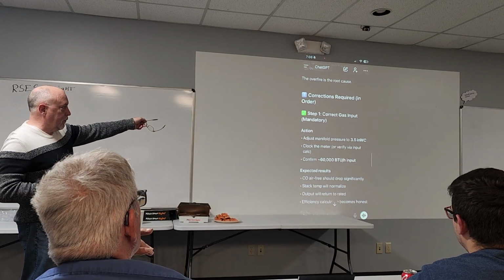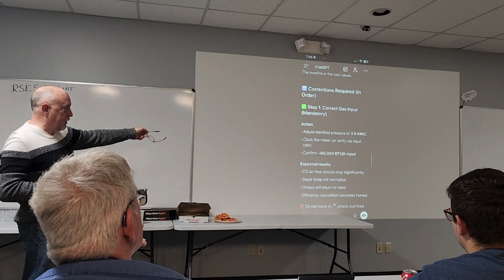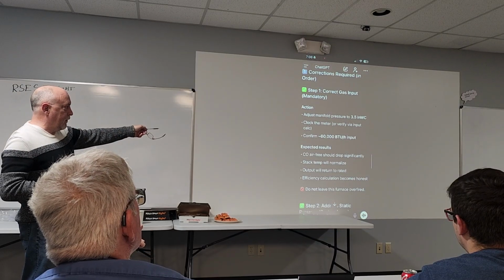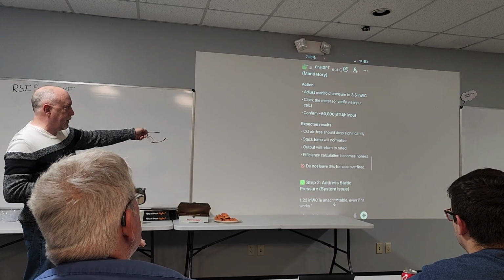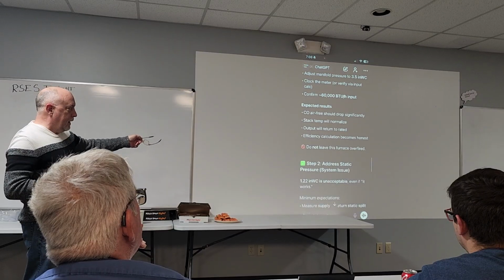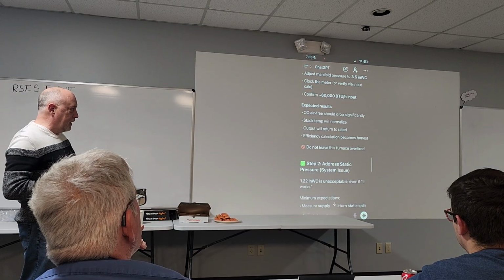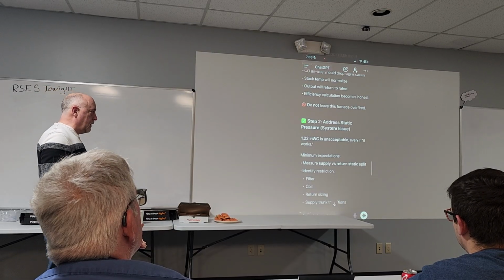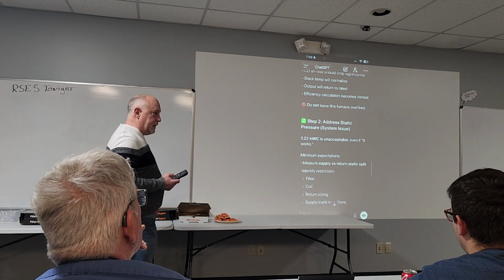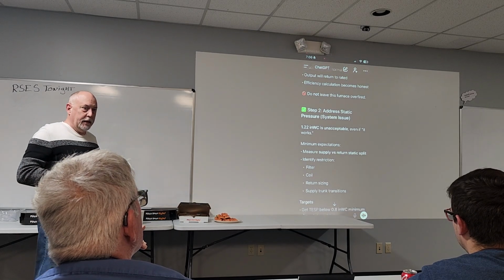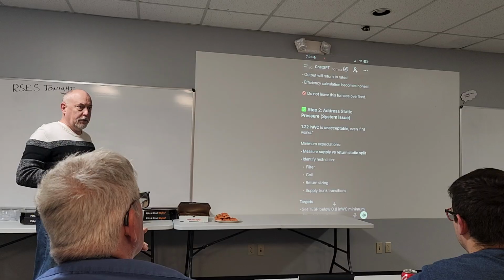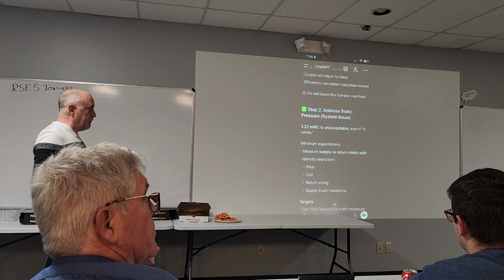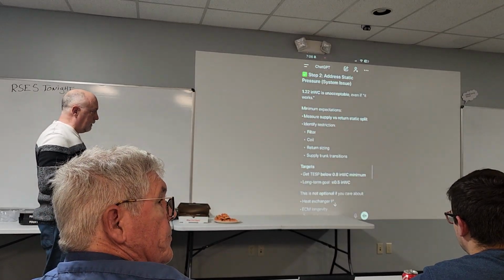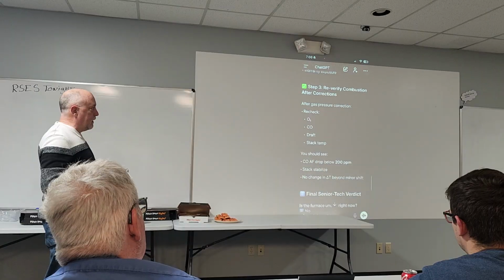Now, adjust the manifold pressure, clock the meter, verify the input, confirm. CO air free drops significantly, stack temperature will normalize, output will be in range. It's not all bad, but it does give you bad advice. So it's about 90% right, and this is why we don't rely on it in MeasureQuick to troubleshoot these problems. We'll let it do some things, but not everything. And then re-verify.